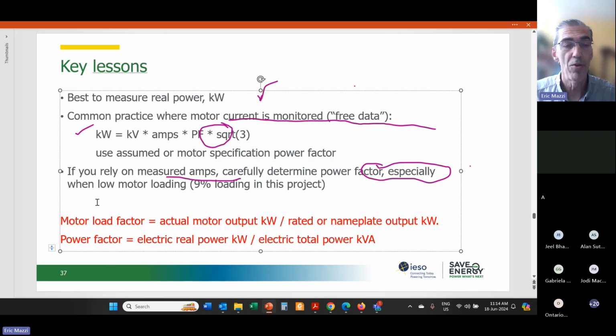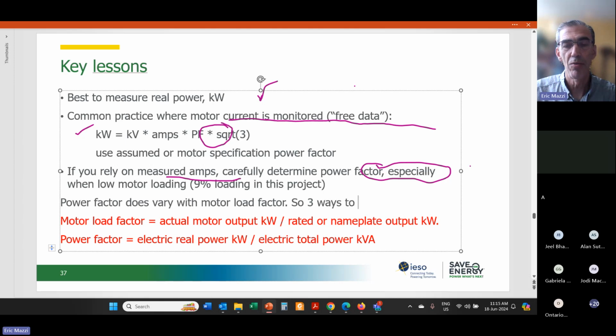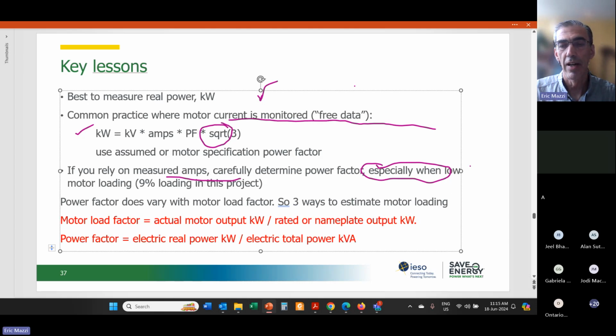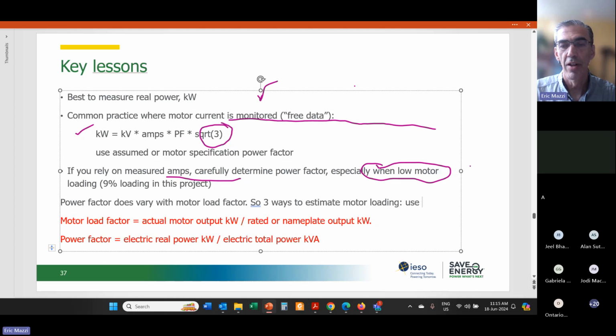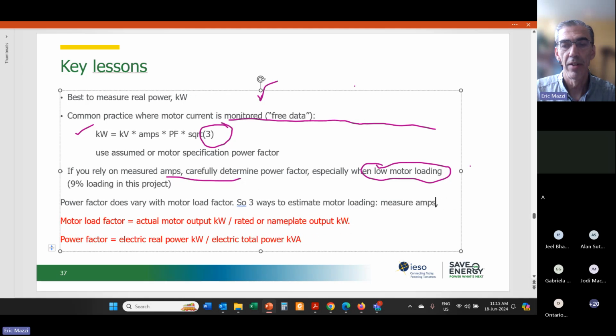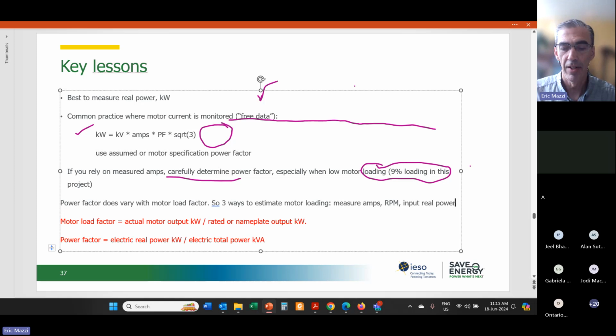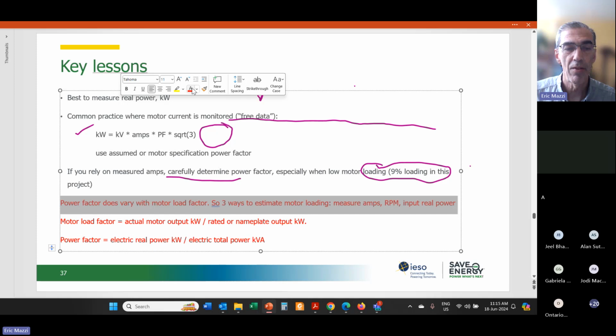And maybe I'll just say one more thing, Edwin. Motor loading, power factor does vary with motor load factor. So three ways to estimate motor loading are: measure amps, measure RPM, measure input real power. This is sort of digressing a little bit, but yeah.